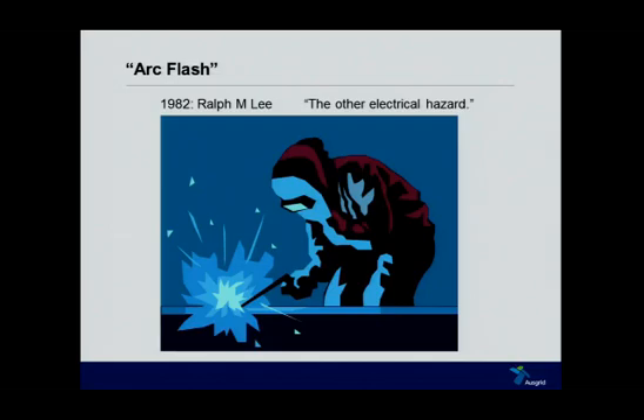Now, the early understanding was very similar to a welding flash injury, in that the energy was transferred by radiant energy. A welding arc, as small as it is, generates a large amount of radiated energy, light in all spectrums, infrared, visible, ultraviolet, X-ray, sufficient to cause flash injuries to your eyes or burns to your unprotected skin. So their thinking was that if a welding arc could generate enough radiated energy to burn you, an electric fault arc, because it's so much bigger, must generate so much more radiant energy, and that's what causes the burns.